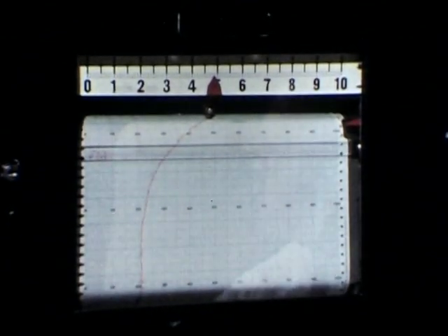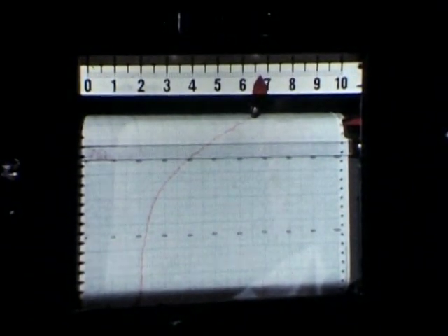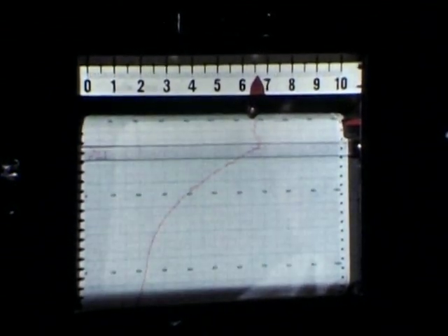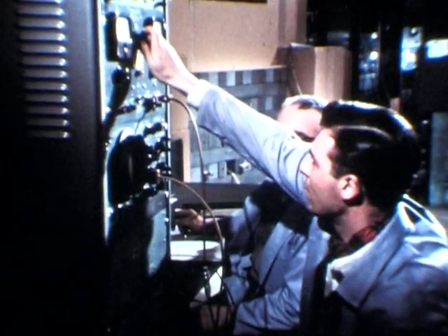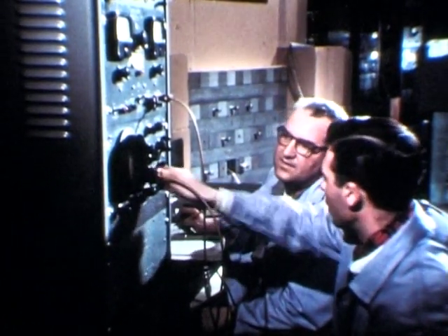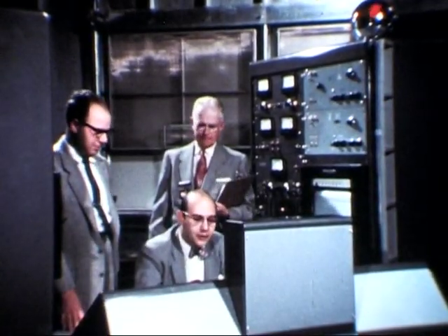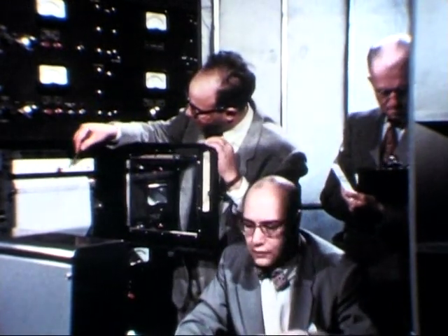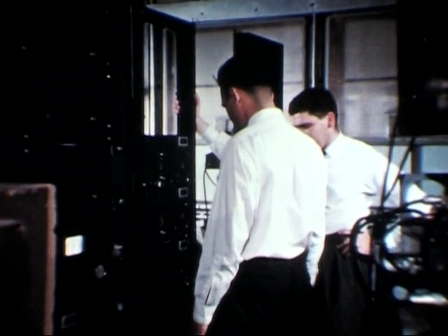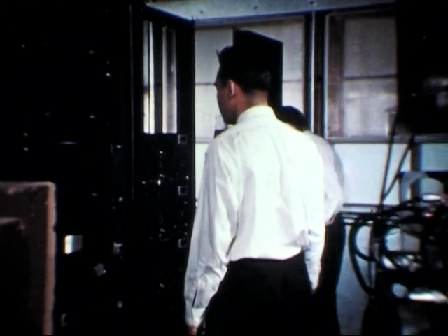The Argonaut has a dynamic range of power from milliwatts to kilowatts for test purposes. The desired reactor power is established by adjusting the fine control rod position. At operating level, the thermal column provides a convenient source of neutrons for calibrating boron-coated ionization chambers for one of the laboratory's critical facilities. At the console, control rod design calculations are verified experimentally by the rod drop technique, the rod worth being proportional to the instantaneous decrease in power caused by the rod drop. Neutrons from one of the horizontal holes are sorted according to velocity by students from Brazil using Enrico Fermi's original neutron chopper.